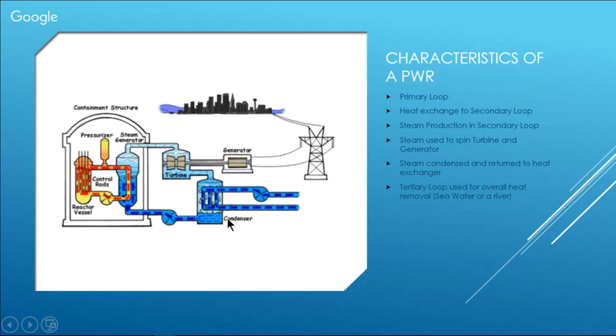So someone asked about cavitation. What he's talking about, we want this water in here always to remain water. The reasons for that are, one, water is a much better moderator, and it's also a better transmitter of heat. When you have steam in here, it'll be a very poor conductor of heat. You can have thermal damage to the control rods and to other things in the reactor. So we want this to be under pressure all the time, and I think you have an upcoming slide that explains how that's done with the pressurizer. Steam can also generate lots of physical damage to the containment system.